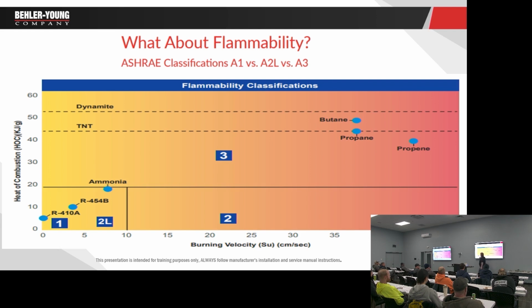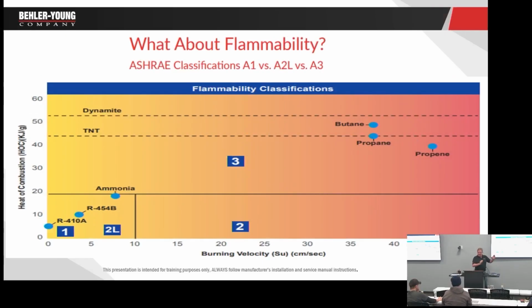If we look at 410A, it's not flammable. It has zero flame spread. 454B is just across the line from 410A, so it just falls into the flammable category. So they had to create a whole new grouping for it. Instead of A2, it's an A2L, because an A2 is flammable. A1 is not. A2L is slightly flammable. The burn rate is less than half a mile per hour. The average person walks 3 to 4 miles per hour, so you can outwalk it. It's a very low flame spread. And if you look at the two side by side, it's just across that imaginary line, making it flammable.